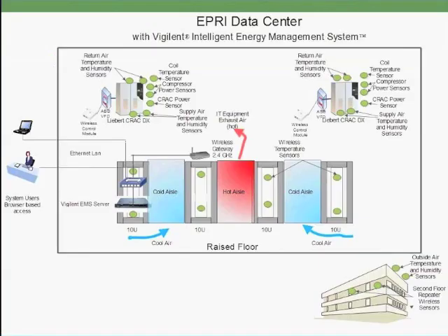What EPRI did over the last year is we took our own data center and we worked with Vigilent to install their intelligent energy management system. The data center that we have here in Palo Alto, California, is about 12 years old, and it has a pretty good hot aisle cold aisle arrangement. There's no containment anywhere. There are two 30-ton direct expansion CRAC units, and each of those 30-ton CRAC units has a 10 horsepower motor to drive the fan that was also about 12 years old. It's not rated for being run by a variable speed drive, but it works just fine.